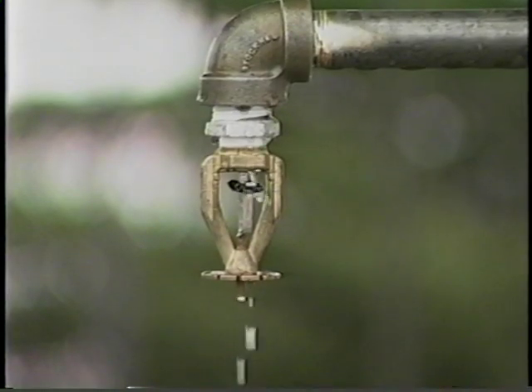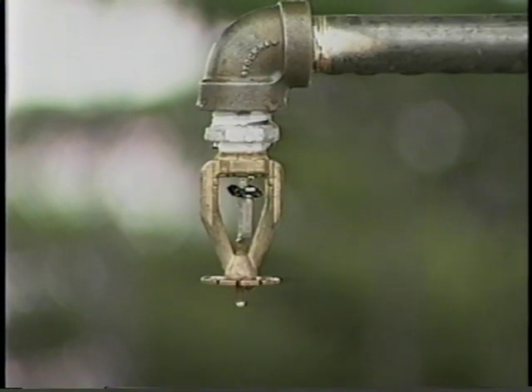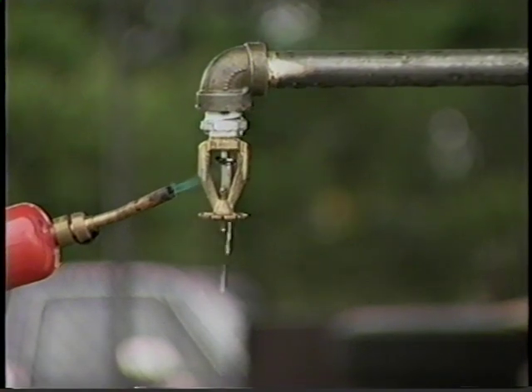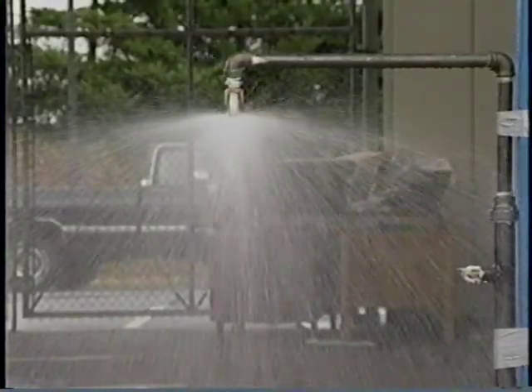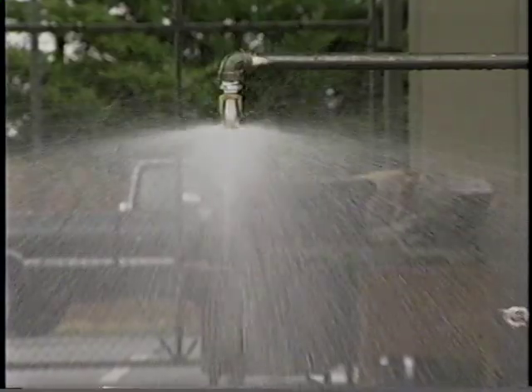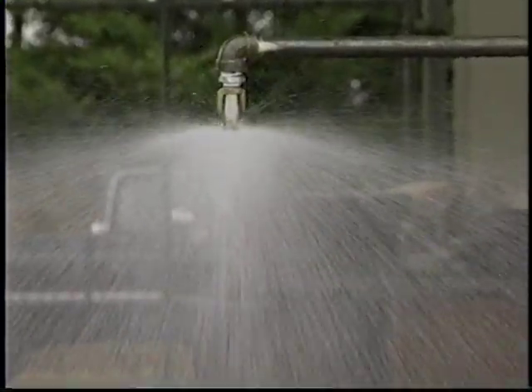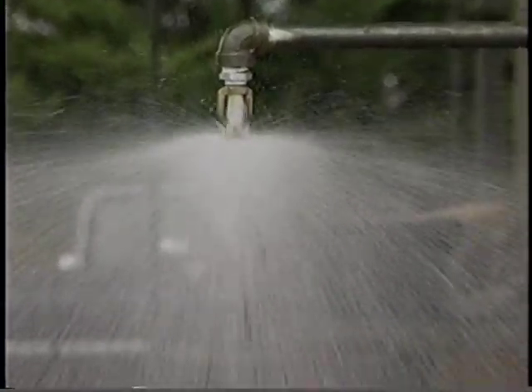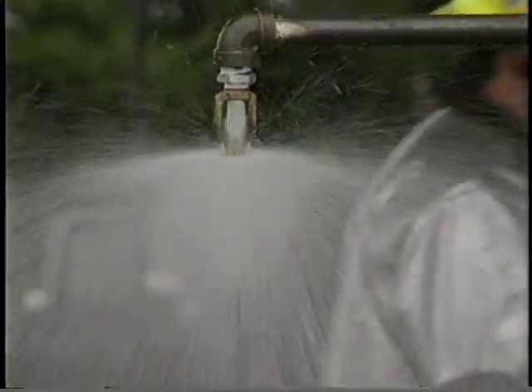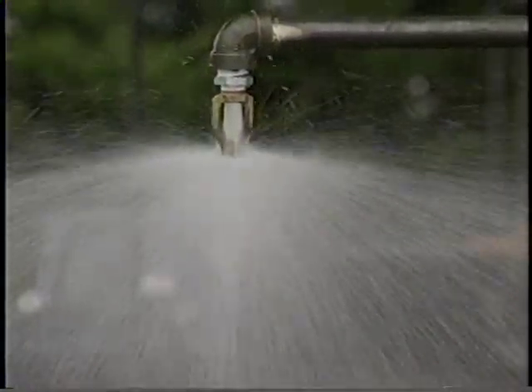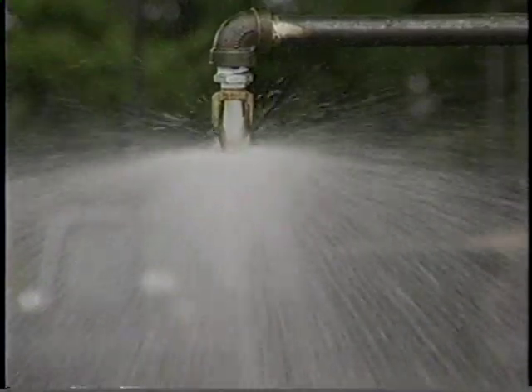The quick response mechanism was specifically developed for life safety purposes. This specially designed fusible link sprinkler has a larger surface area to collect the heat generated by a fire. This results in a faster opening of the sprinkler and quicker extinguishment of the fire.